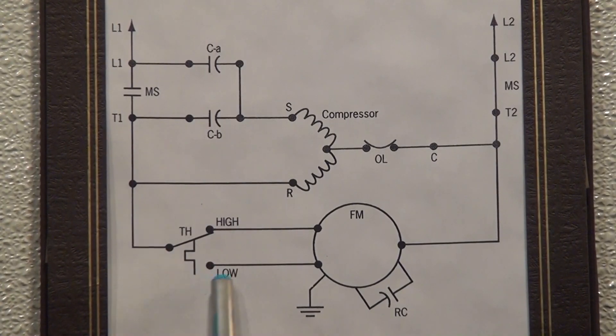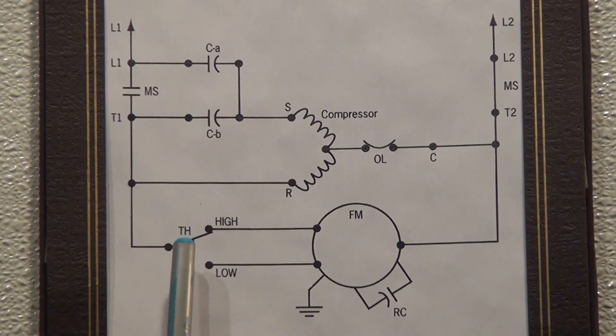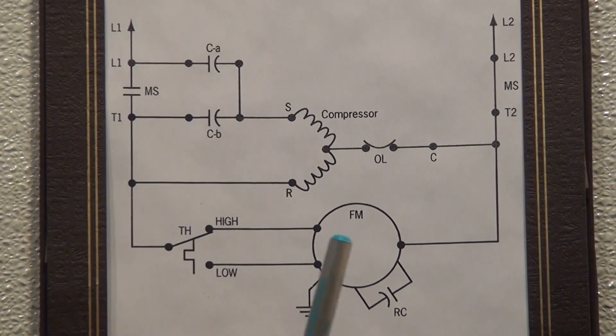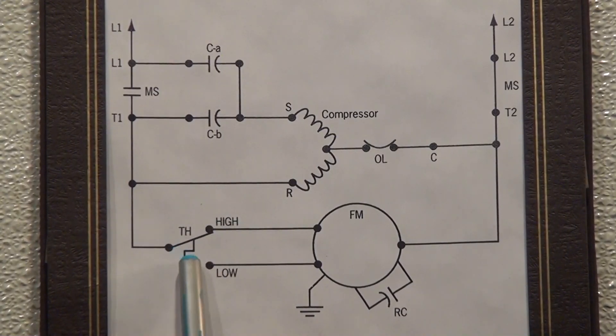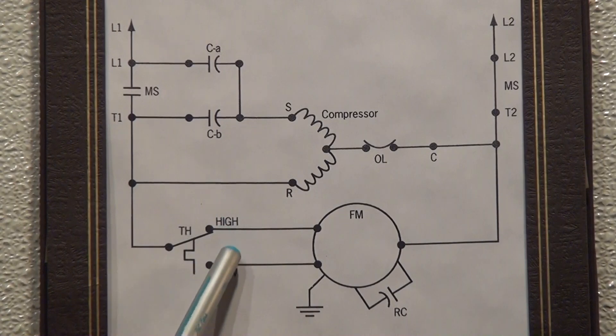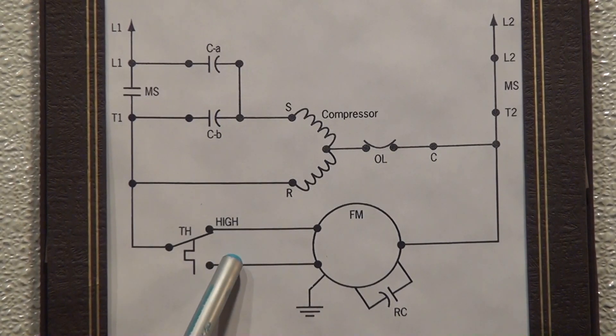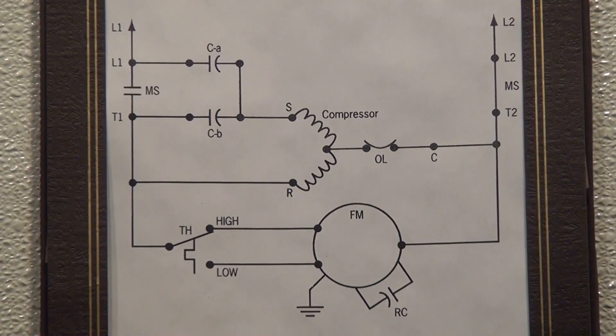Now the other thing we want to talk about here is this device right here. This device is an outdoor fan motor thermostat. Since it's a heat pump, we have a situation where this manufacturer has decided that in a low ambient situation and a higher ambient situation, we'll be able to go back and forth between a high and low speed with the outdoor fan motor in order to maintain proper high side refrigerant pressure.